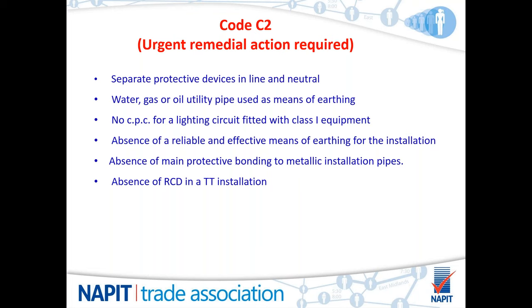And as long as there's no fault developing, then there would be no problem. There is a problem, though, if a fault develops and somebody decides to change the light fitting or touch the light fitting with a fault on, no CPC being present, they obviously become that earthing conductor. Any absence of reliable and effective means of earthing, if there's no earth, protective devices will not work. Main protective bonding conductors missing to metallic installation pipes. The pipework will remain A-OK for as long as there's no fault, but the minute a live conductor touches it, then obviously somebody could have a shock risk.